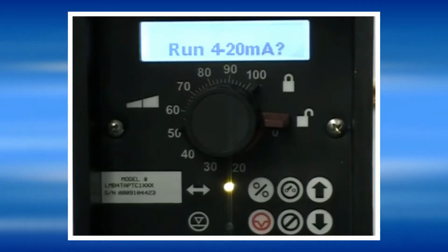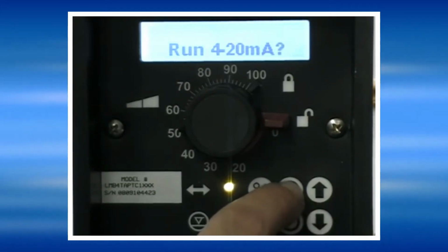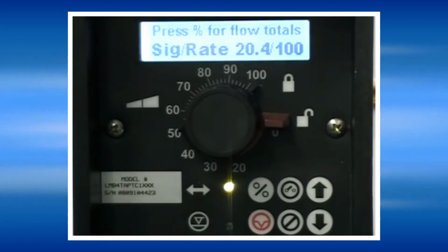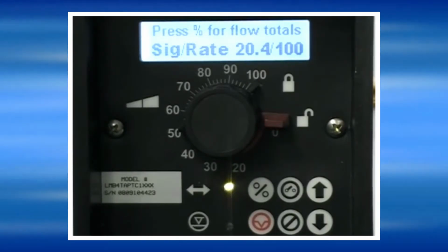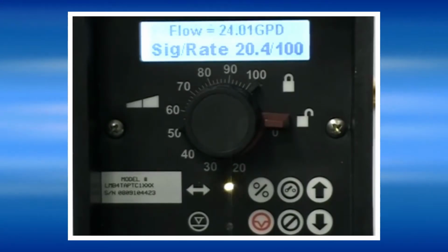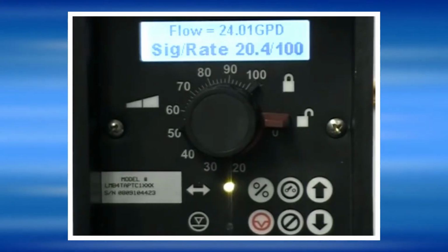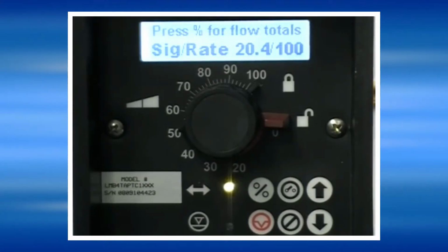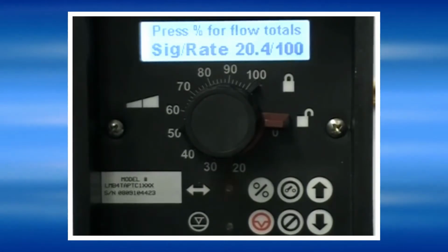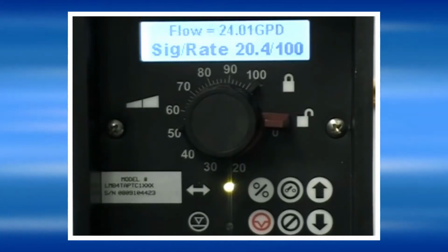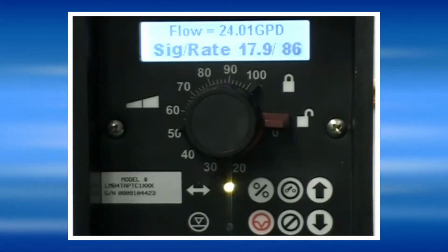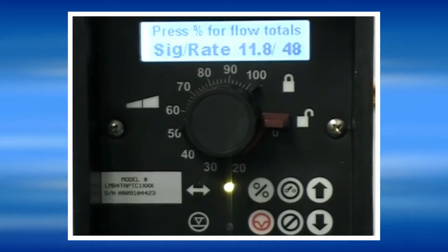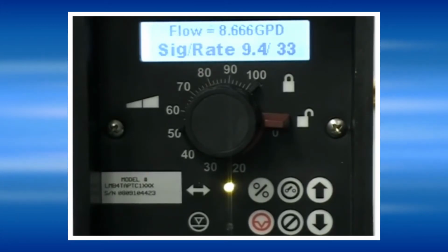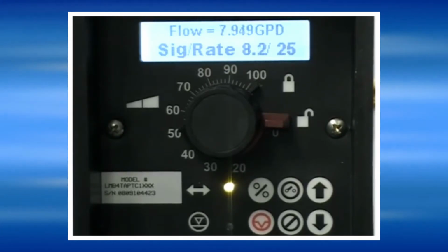To run the pump in the 4 to 20 milliamp mode, simply press the Yes key. The pump will then operate responding to the 4 to 20 milliamp signal as we just programmed it for. The pump displays that it's receiving 20.4 milliamps at the moment and running at 100% speed. As the milliamp signal is decreased, the pump speed also decreases proportionally based on the way that we programmed the high and low rate settings.